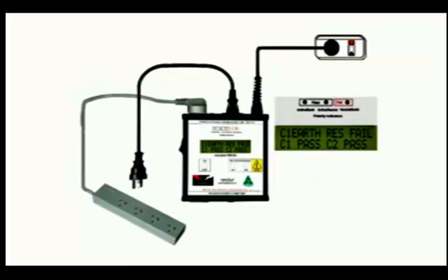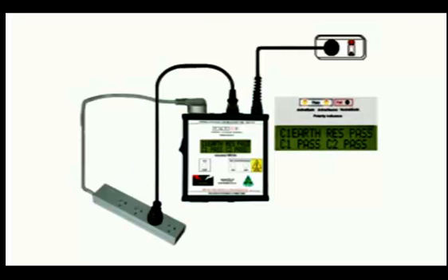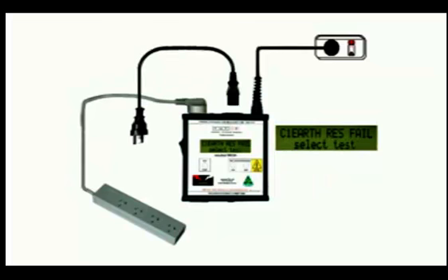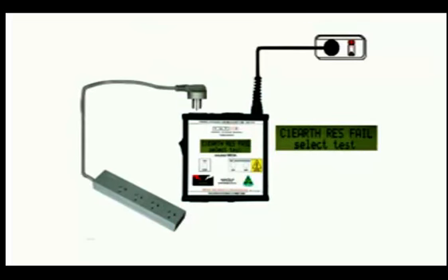Test completed, well, for a standard extension lead, but since this has several outlets, we'd best check them all. And as long as we have passes on the lights and both lines of the display, the device passes. Now the test is completed. It's that easy. Switch off, unplug it, and tag it.